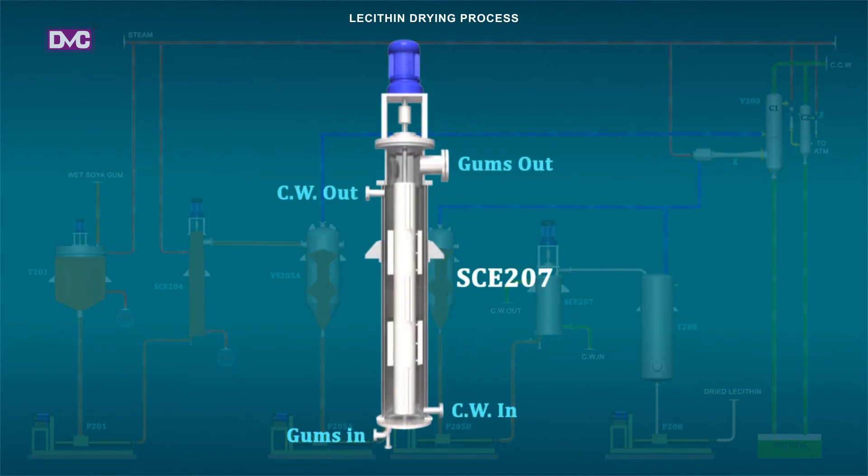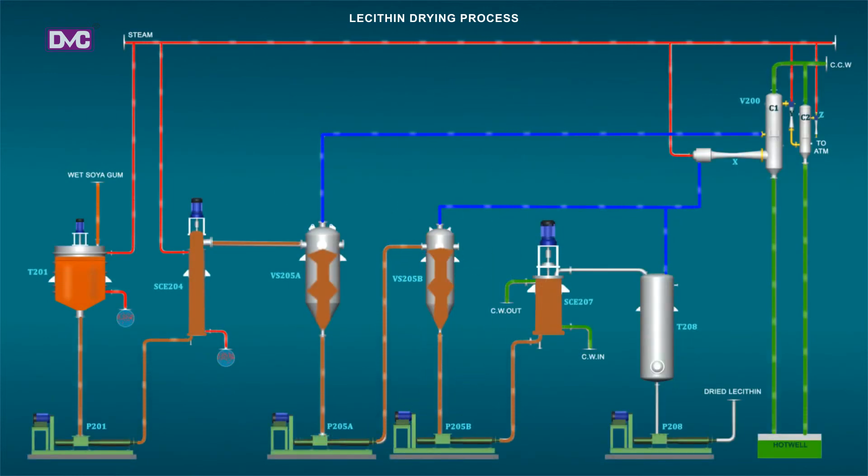The dried gums are conveyed by pump P205B to final cooler SCE207. The cooler is a rising film type scraped surface cooler, working under a pressure of 5 bar. Through the shell jacket of the cooler, cooling water is kept under circulation to cool down the product to 50 to 60 degrees Celsius prior to sending it to the intermediate storage tank T208.